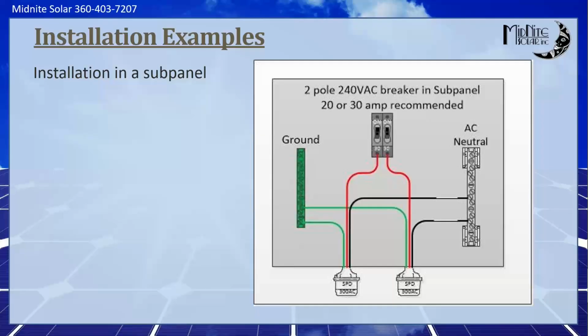And 99% of the time, the ground and the neutral are separated in that subpanel. And we need to protect the neutral because the neutral is bonded back at the main panel, but 300 feet away during a lightning strike, it's technically not bonded anymore because the resistance in that wire is going to let that voltage go crazy. Think about taking, say, 1,000 feet of 12-2 wire and trying to run 10,000 volts across it. If you're running 10,000 volts at, say, 5,000 amps, by the time you get to the other end, you're going to have like a tenth of that voltage. Well, you're going to have burnt up wire, but that's a different story. The voltage drop would be incredibly insane. And this is a very common failure point that we see: the neutral doesn't get protected in those subpanels.